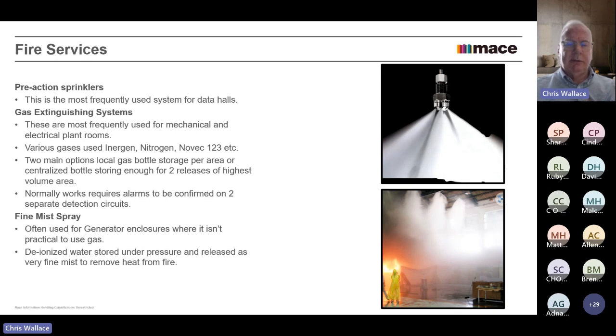And obviously, you talked about generators before. There are lots of generators on these jobs. You're not really going to do any good with a gas, and you don't really want to put them through the sprinkler system. So quite often the generator enclosures or generator rooms are fitted with a fine mist sprinkler system, and they would use deionized water under pressure in some sort of pressure vessel, and then just put it in as a fine mist in the event of a fire. Lots of other things we could talk about on the fire services, but that's generally the main thing.